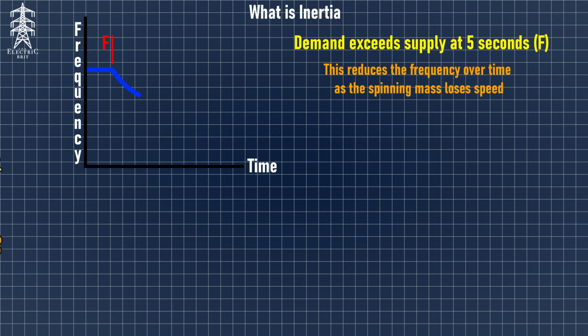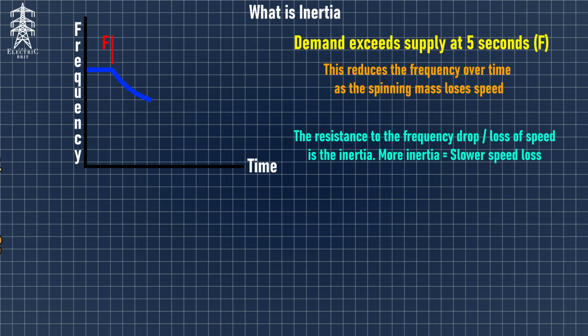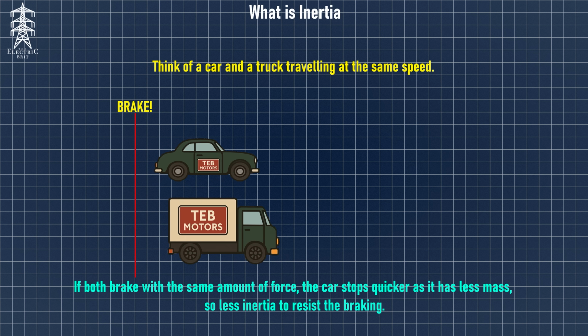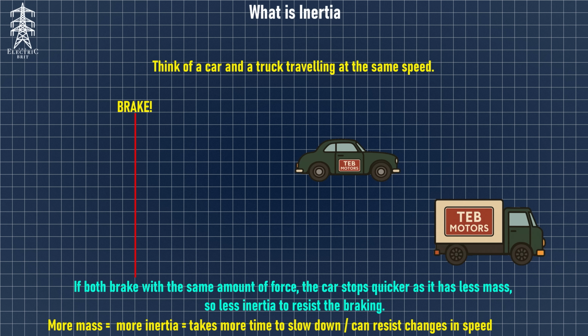That resistance buys time, seconds, for the rest of the grid to respond. Without that, the frequency would swing too fast, too far, and risk a blackout. The more mass we have, like the truck in this example, the more inertia we have and the longer we have to respond. So what makes synthetic inertia synthetic?